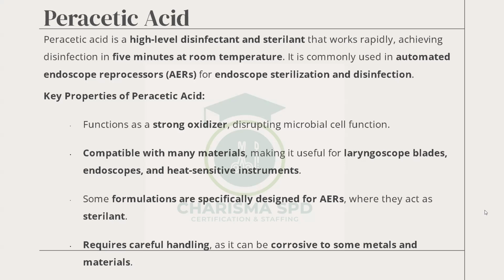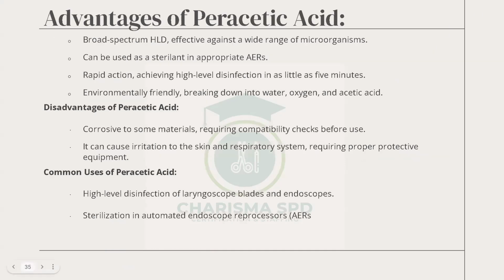Next slide, please. We are gradually getting to the end. Don't worry, guys. I know it has been a marathon day. Advantages of peracetic acid. Broad spectrum high-level disinfection, effective against a wide range of organisms. It can be a sterilant, of course, we said that already, in the AERs, automated endoscope reprocessors. Rapid action, achieving high-level disinfection in as little as 5 minutes. Remember, we said the alcohol must remain in wet contact, and alcohol is not a high-level disinfectant. But this one is a high-level disinfectant. 5 minutes, and the job is done.